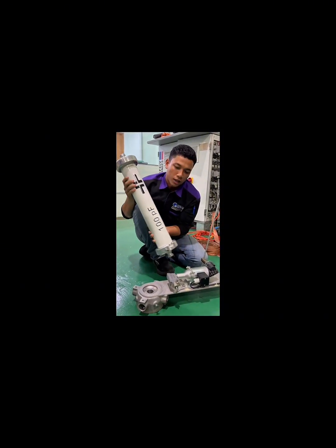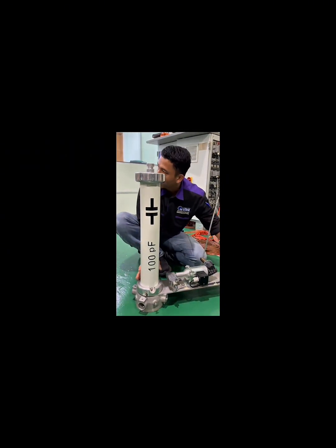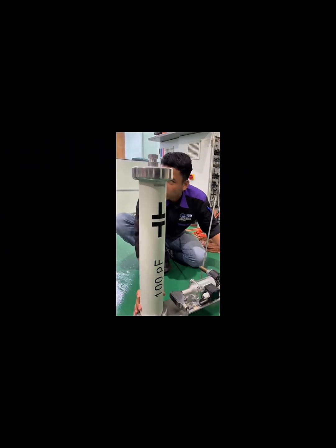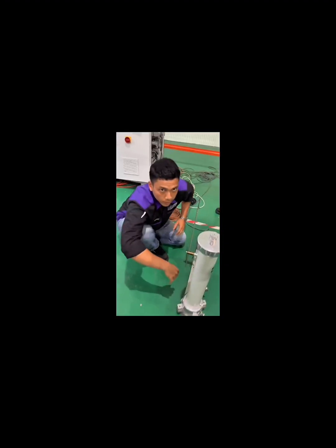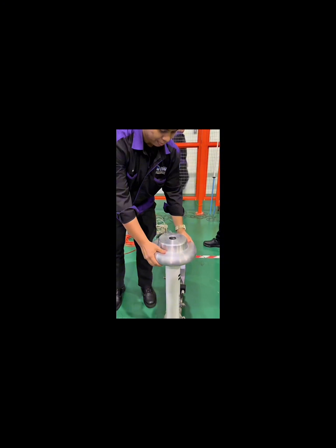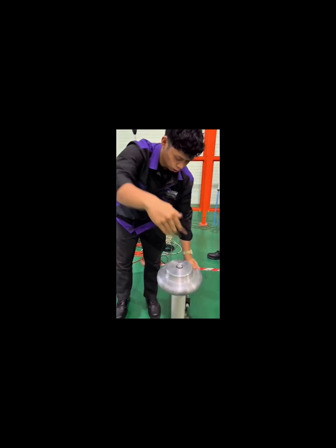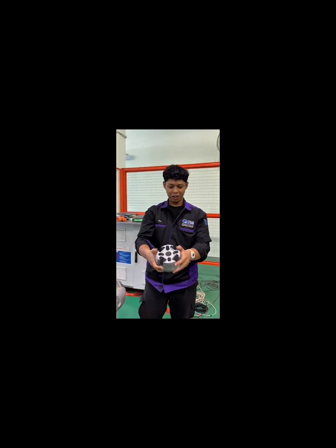Okay, third, we use a 100 kV measuring capacitor that functions as the HV unit for the AC voltage divider. So we plug it in the floor pedestal. The electrode is the part that directly contacts the test object or medium, such as insulation material or dielectric fluid in high voltage testing. It allows voltage to be applied across the insulation being tested.